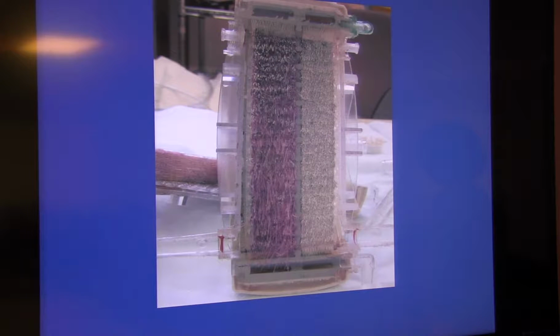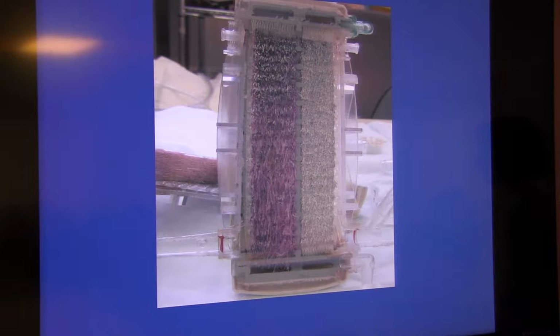Where's the temperature? Which screen is the temperature? Temperature doesn't show, so the temperature gets set on the heater down here, and back here there's a little digital display which will tell you what it's set for, but not your patient's temperature. Is there a standard temperature that you guys set here? That's a good question. What's the standard temperature that we usually set, Kim? 36? It'll vary a little bit, somewhere between 36, sometimes up to 38, depending on the air conditioning in our rooms. And if we're cooling, we set it a little bit lower.